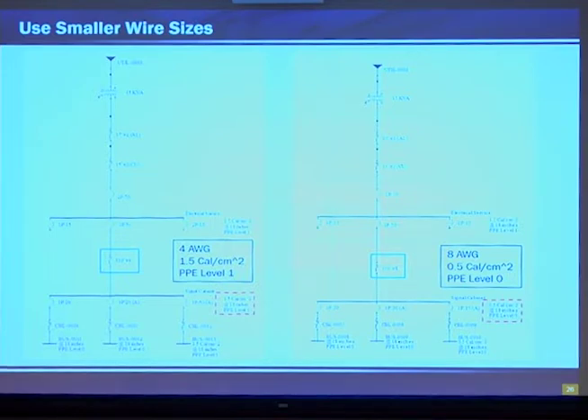So we know it works in the design phase, but here's something that works on both existing and on a design stage. Say you're going from the existing service to the signal cabinet, going from a number 4 to a number 8. You reduce the incident energy from 1.5 calories per centimeter squared to 0.5 calories per centimeter squared, reducing the PPE level from a 1 to a 0. I promise you, your maintenance crews and anyone going out there looking at that will be very happy going from wearing a face shield to wearing untreated cotton. I promise you that, being arc rated to not having to worry about losing an arm, they'll be happy.